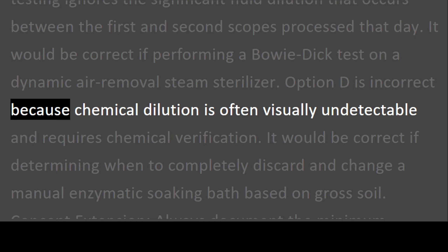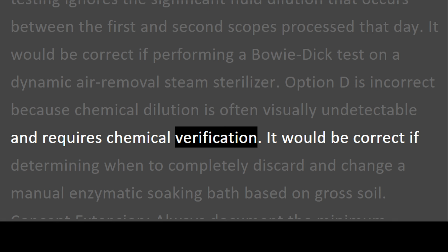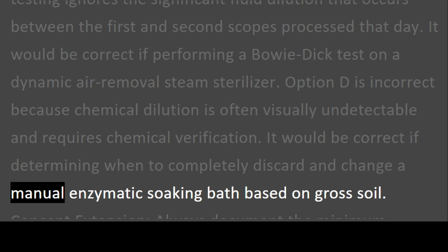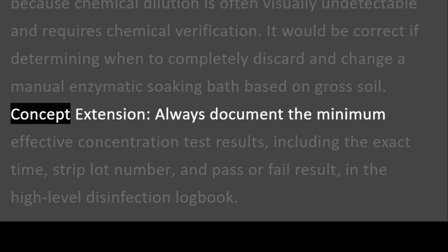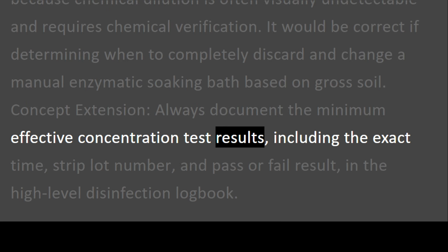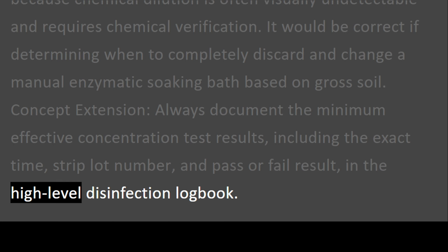Option D is incorrect because chemical dilution is often visually undetectable and requires chemical verification. It would be correct if determining when to completely discard and change a manual enzymatic soaking bath based on gross soil. Concept extension: always document the minimum effective concentration test results, including the exact time, strip lot number, and pass or fail result, in the high-level disinfection logbook.